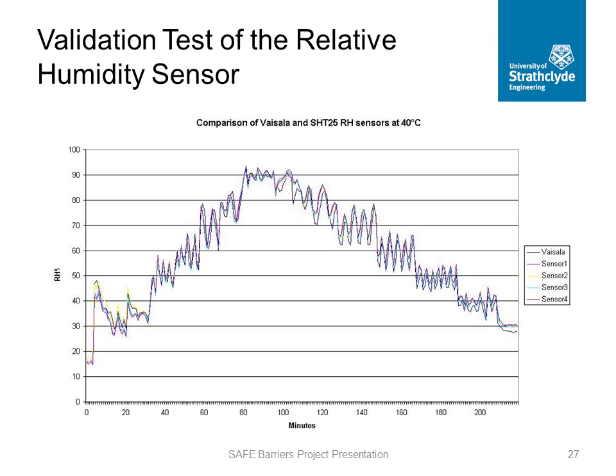The same experimental setup has been used to compare the relative humidity inside the chamber measured by different sensing instruments. Four relative humidity sensors, together with the Vaisala relative humidity probe, are installed inside the chamber, and the relative humidity level inside the chamber are imposed as increasing and decreasing steps from 30% to 90% and then back to 30%. From this figure, we can see that the relative humidity measured by four sensors and the reference probe are quite coherent during the increasing cycle of the relative humidity, while the discrepancy is higher for the decreasing cycle after the long exposure of relative humidity sensors to a humid environment.